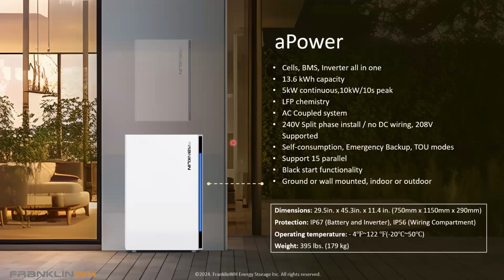It is AC coupled. You feel secure that not only does it work in every situation, but because we're AC coupled, we have additional power available. So we're not limited by an inverter output. Our system outputs 5 kilowatt continuous, and then any production from the solar would also be available for that continuous output. So if you had 7 or 8 kW of solar and a 5 kilowatt battery, your potential is more than 10 kilowatt of continuous power through this system. So AC coupling does have its advantages.